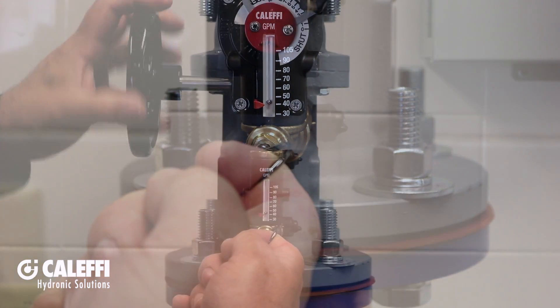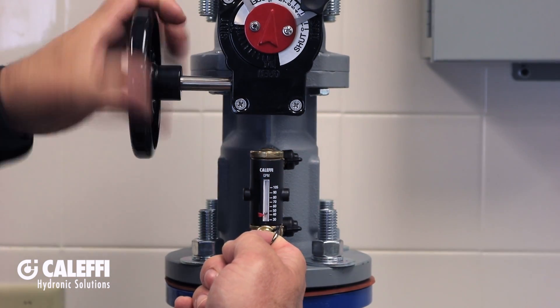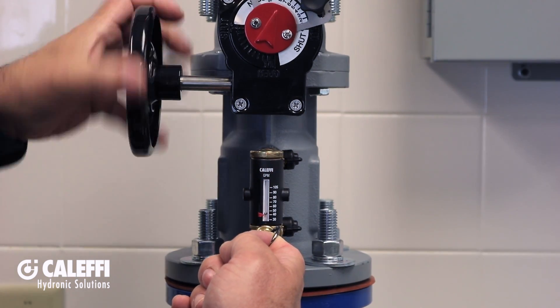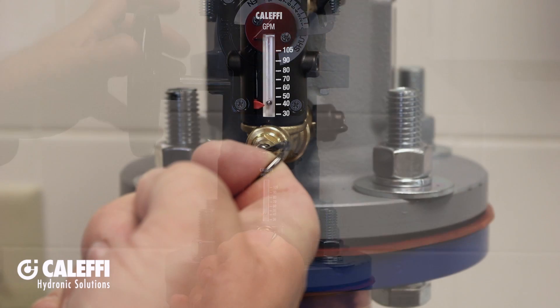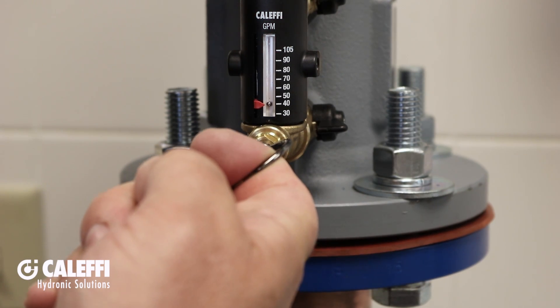I'm going to just adjust my hand wheel until the flow indicator bead aligns with the design flow rate pointer. When they match, release the pin and the circuit is balanced.